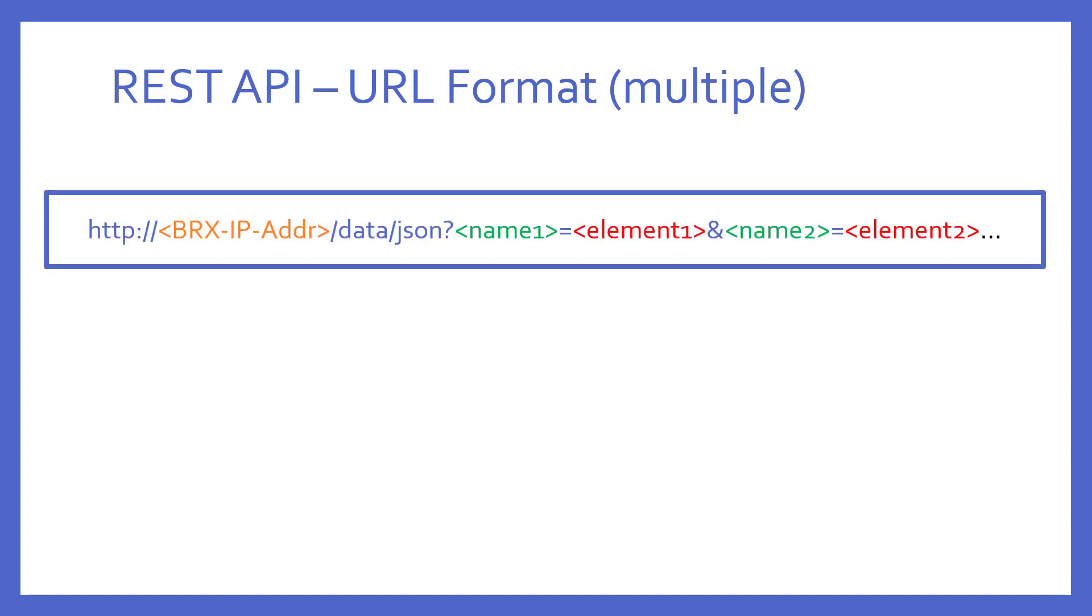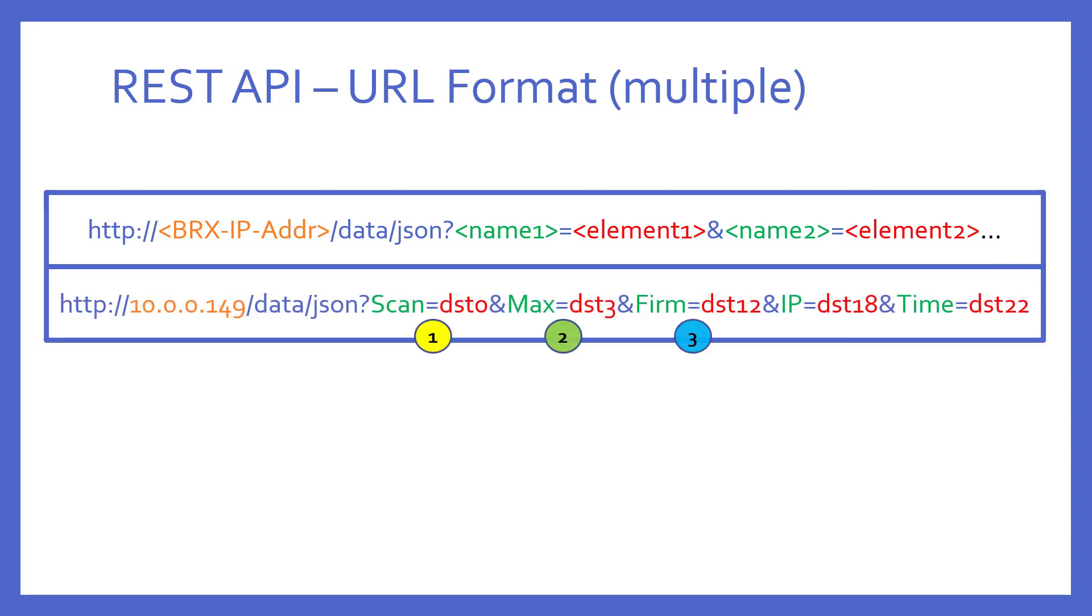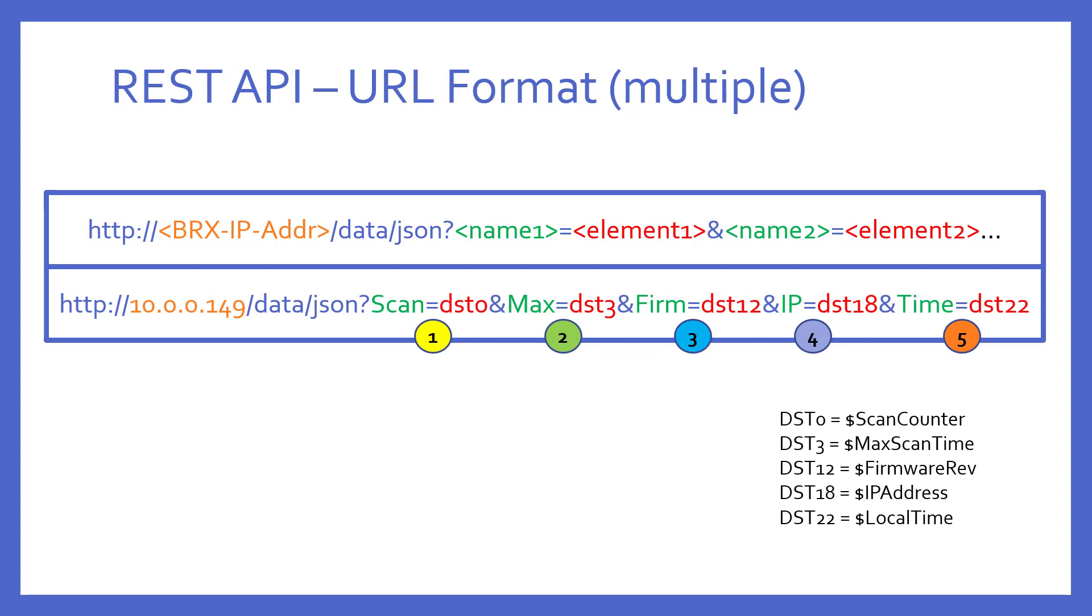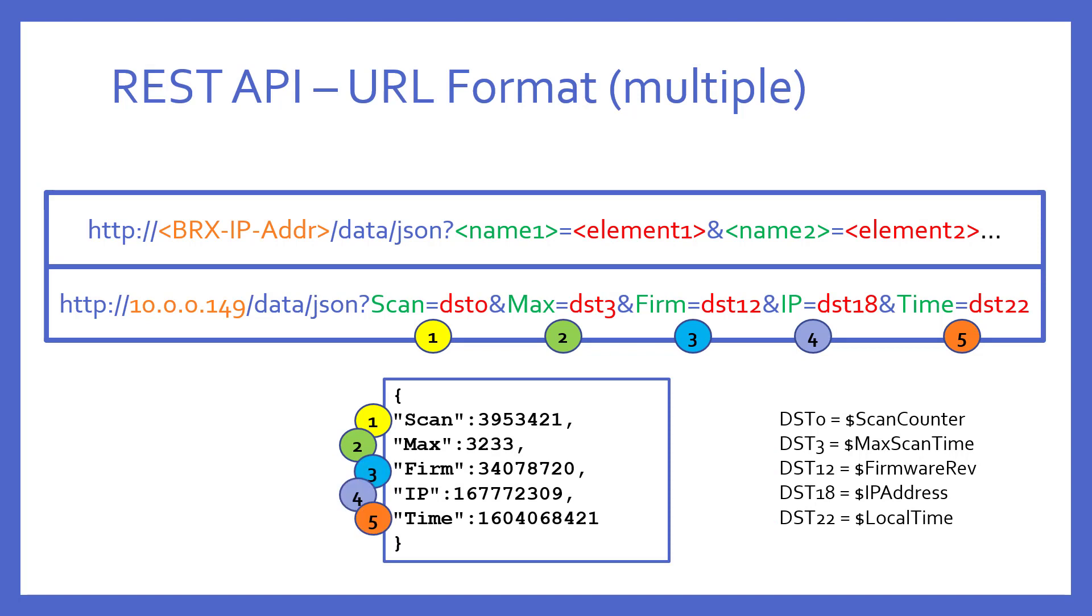So, what if I wanted to get several non-contiguous elements? Notice all that is needed is to append another name equals element by using an ampersand. The dots at the end here just mean etc. So, in this example, I'm getting five elements separated by ampersands. I'm asking for several non-contiguous system data double words, DST0, 3, 12, 18, and 22. The result looks like this. Again, it's a JSON object, but it contains multiple name value pairs properly separated by commas and using the names that I gave each element.